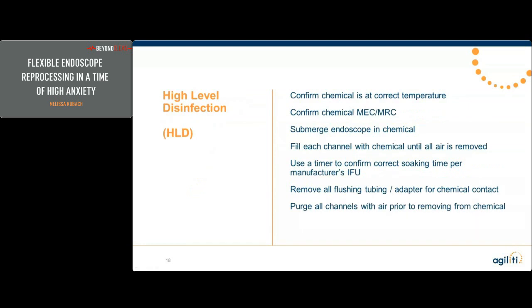High-level disinfection: we want to confirm chemical is at the correct temperature, confirm chemical MEC or MRC, whichever way you call it, is being done, and submerge endoscope in the chemical, fill each channel with chemical until all air is removed, use a timer to confirm correct soaking time per the manufacturer's IFU, remove all flushing tubing and adapters for chemical contact, purge all channels with air prior to removing from chemical.